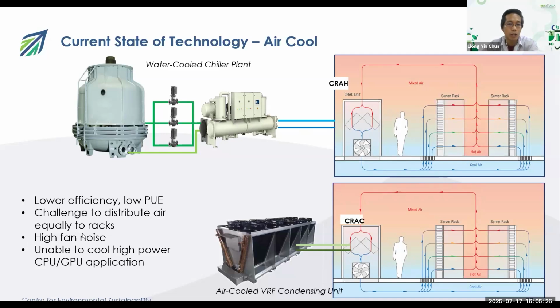There's also a challenge to distribute the air equally. Imagine a huge data hall with all these racks — the rack at the furthest end would probably get less air, because most of the air goes through the nearest racks first. Even if you balance the racks and dampers properly, most of the cold air will still tend to go to the bottom racks, because as air escapes, there's less air left at the top to cool the servers there. And since you're using fans, you also get high fan noise.